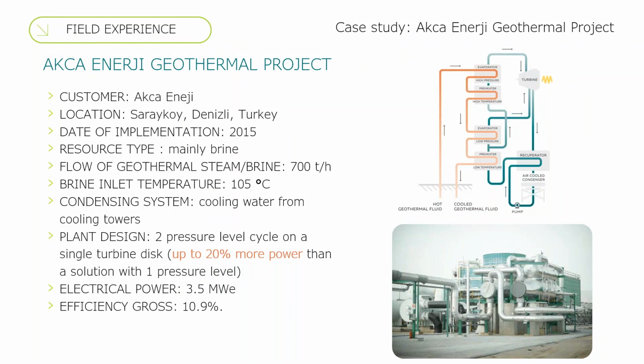In this combined steam brine geothermal ORC, the design was studied in order to develop a two-pressure cycle ORC plant, meaning there are two evaporation stages at different pressures. This allows maximizing thermodynamic efficiency while minimizing irreversibility, guaranteeing maximum thermal recovery of the heat resource.